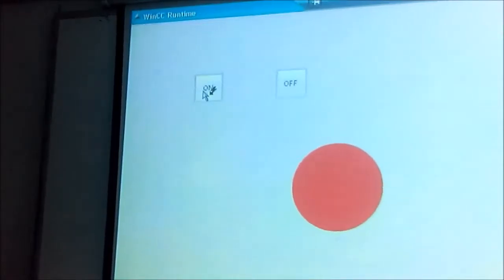So I clicked on off, that has turned off, and again this will turn off because there is a delay that is set by default of 2 seconds. That is why it is getting off with a 2-second delay. Again, just to affirm whether the output is dependent on that output or not, right? I am clicking on here, and I am going to make that output off forcefully because I have already taken a switch, fine. So this is I0.2. I have to draw the signal from here, right? And see that has turned off, fine.